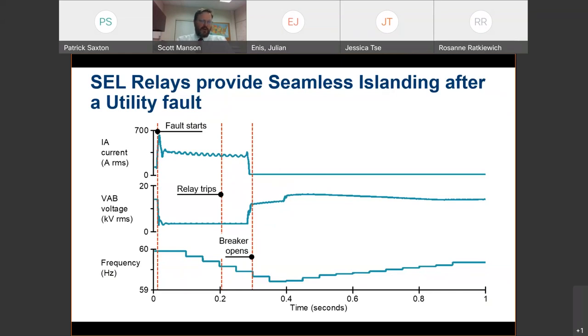A protective relay isolates the breaker, but the job isn't done, because now there's not enough generation, enough inverters, to power your home, to power your business. In this case, it was a large microgrid in the Northeast. At that moment, the microgrid controller, it could have been a relay, in this case it was a small RTAC, detects that the breaker has opened and says, you don't have enough generation to power your load. And I see your frequency is in free fall. Therefore, I will eliminate non-priority loads to alleviate that overburden and stop this frequency free fall.